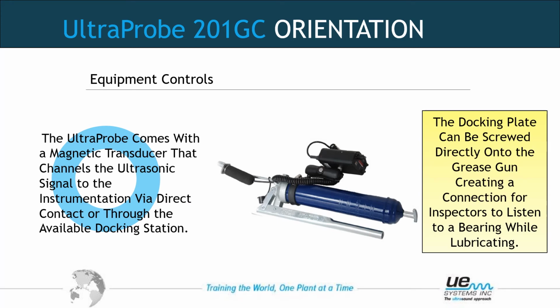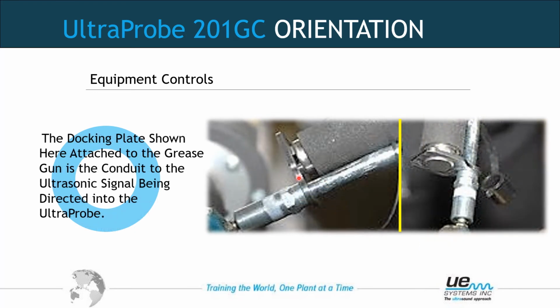The Ultraprobe comes with a magnetic transducer that channels the ultrasonic signal to the instrumentation by direct contact or through an available docking station. The magnetic transducer is put onto the docking station that comes with the Ultraprobe 201 grease caddy. You can attach the docking station to the grease gun. Here we see it attached.